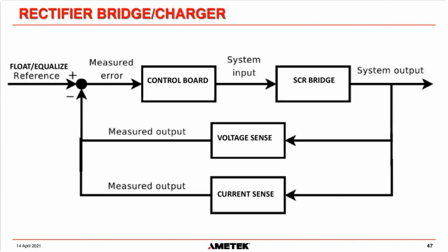And that's exactly the same as a charger feedback circuit. Instead of pressing the button on your steering wheel, we set the float or equalize voltage levels. That measured value goes into the control board, and then the control board sends signals to the SCRs on when to turn on. We're not going to talk about current sensing just now, just the voltage sensing.